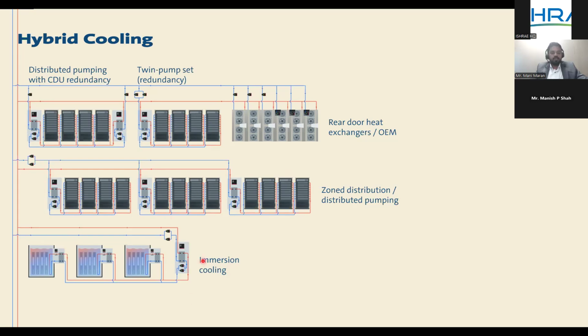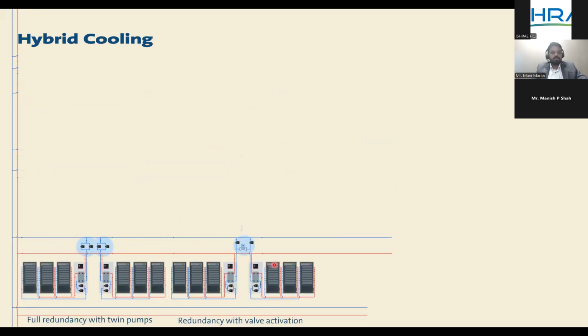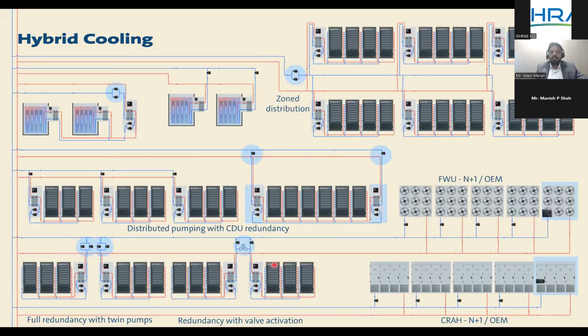And even for immersion cooling, the CDU concept remains the same, and the pumps can have redundancy either on the pump level or on the CDU level, which you can see in the next slide. But this is another set of configuration, and this can work well across all tiers. Even with tier 4, distributed pumping or coil pumping or dedicated pumping can be an ideal fit, and it gives us more flexibility to add load at any point of time without rebalancing the system. That's also one of the beauties of having dedicated pumps for each unit.